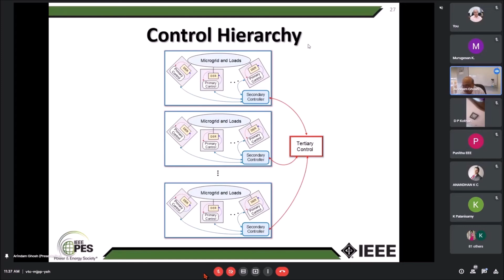Now let's look at what the controllers are. The primary controller is the Droop control, as I mentioned. Remember, Droop control is a steady state concept, in the sense that once your system attains steady state, then you will have this voltage, this power, and this frequency. However, if you have very fast load change, then the Droop controller might cause system instability. So you have to rely on the secondary controller to do correction so that your system doesn't become unstable.